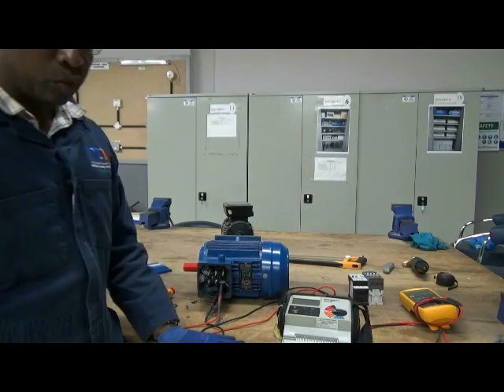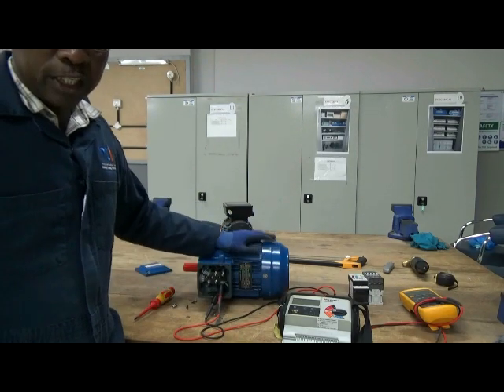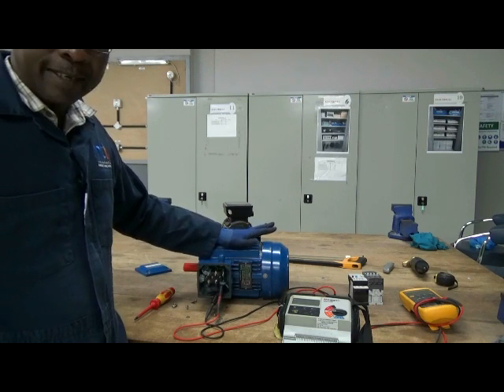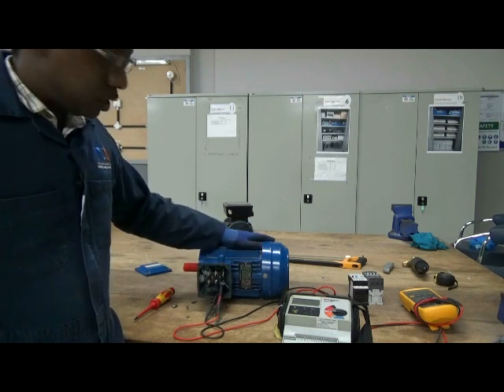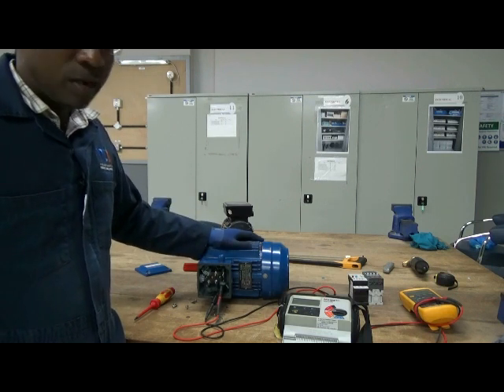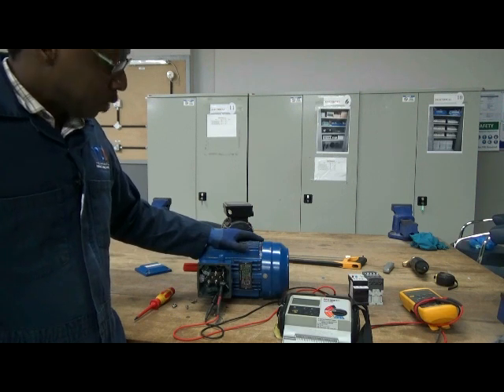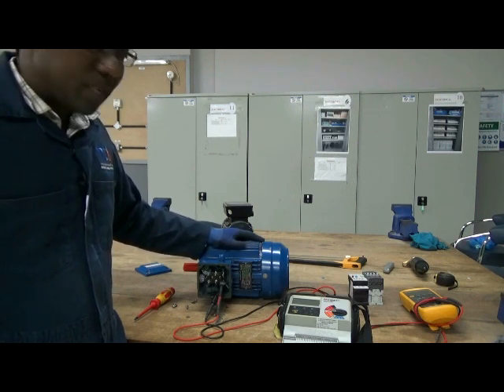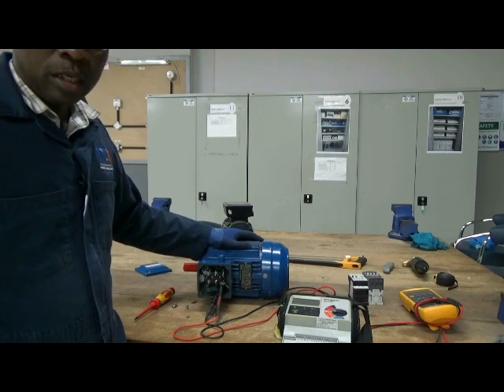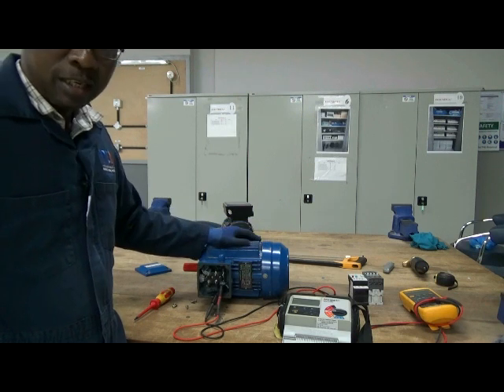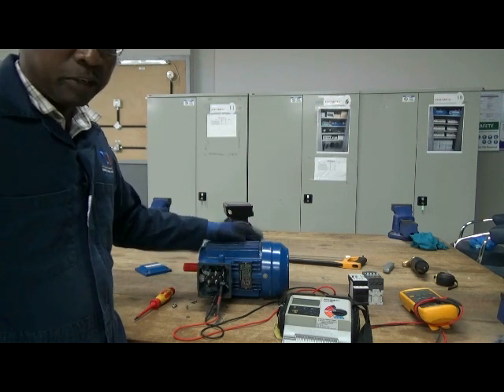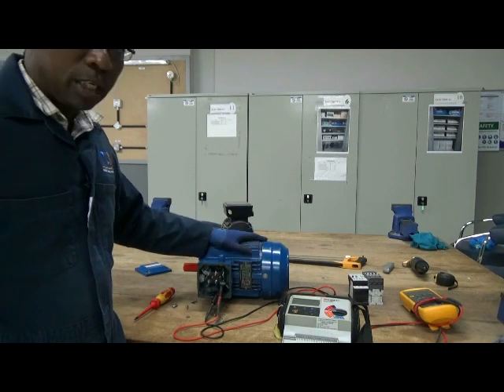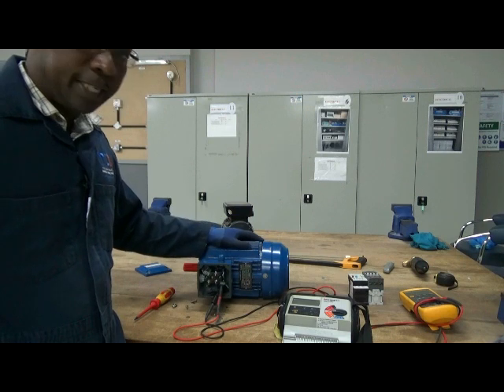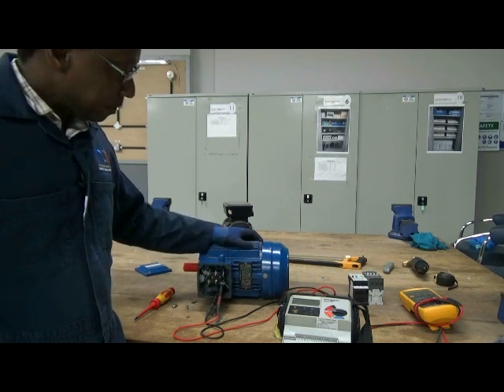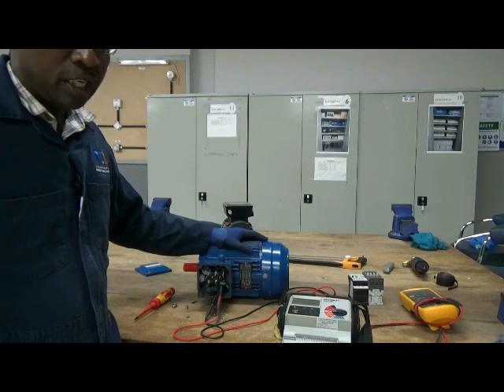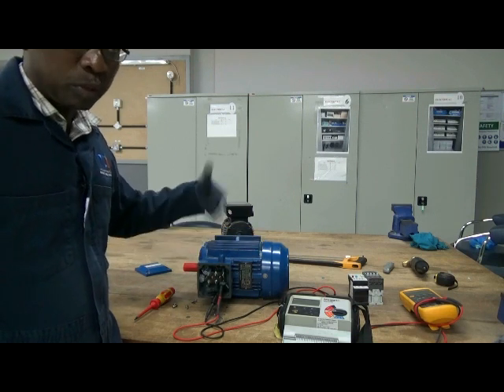But with this instrument, I'm going to induce a voltage, actually a very high voltage, about 500 volts. This is a 380 volt three-phase motor, which means it requires 380 volts to operate. So when I'm doing an insulation resistance test, I will induce a voltage twice as much as its operational voltage. And if it can withstand that, then it means that the machine is good. This is according to the IET regulations. They stipulate that if equipment is operating at a certain voltage, the insulation resistance test voltage which you must induce must be twice as much.